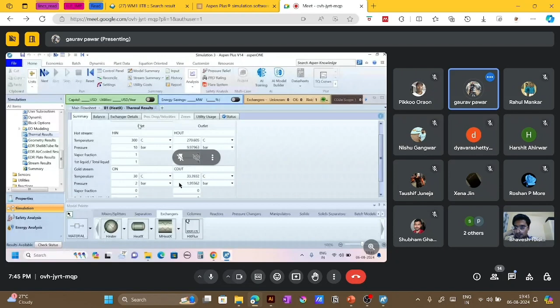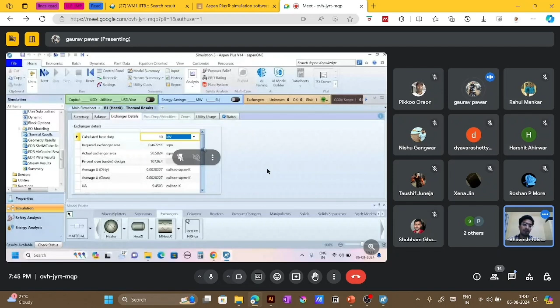So in that case, we have to modify this design. For that, the design we selected, instead of shell tube length of 100, do it 50. Instead of providing a bigger diameter of shell, provide a smaller diameter, reduce the number of passes. That's the sort of thing you have to start with. Now this kind of becomes a combined approach of designing as well as optimization.